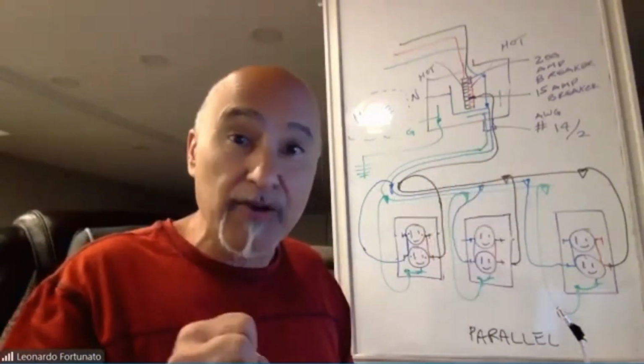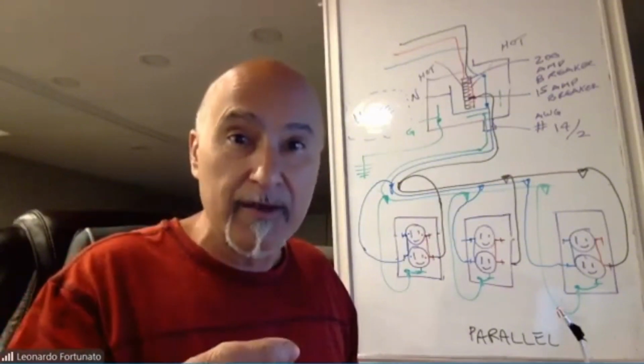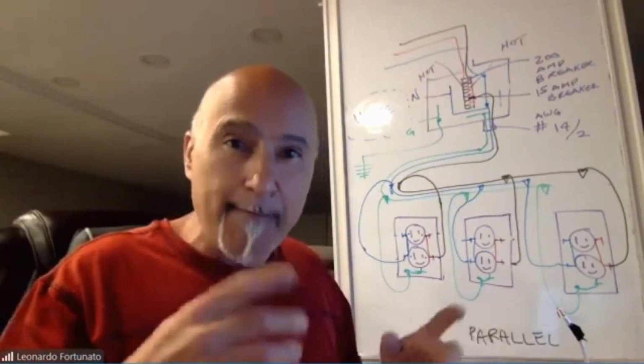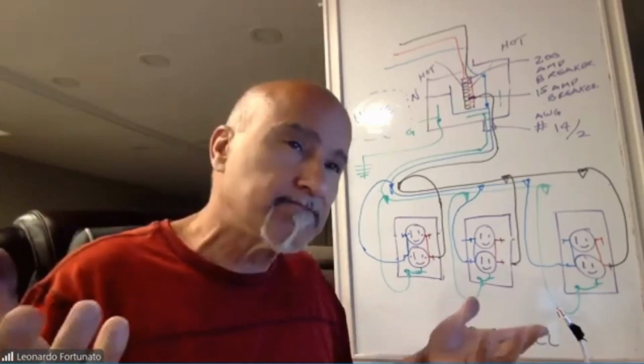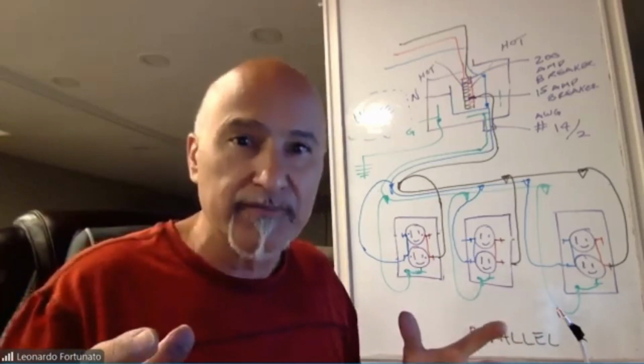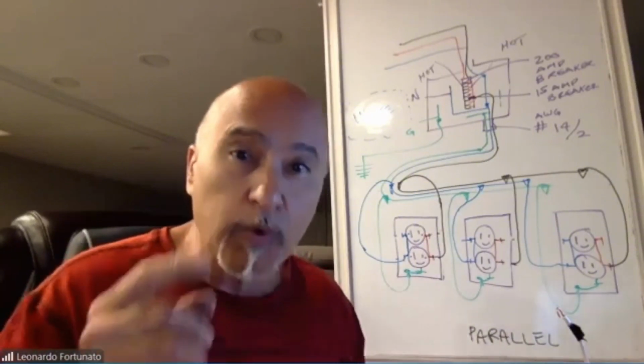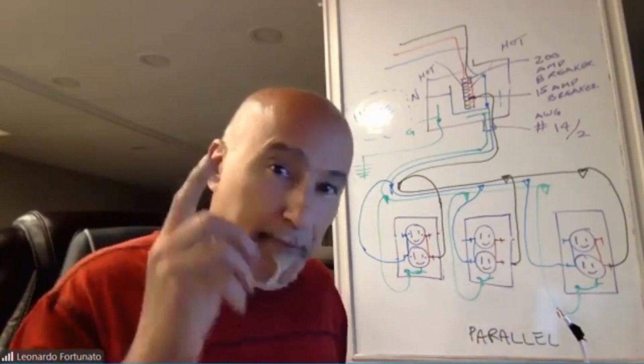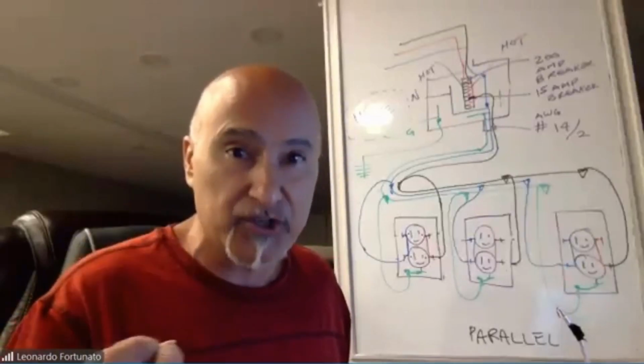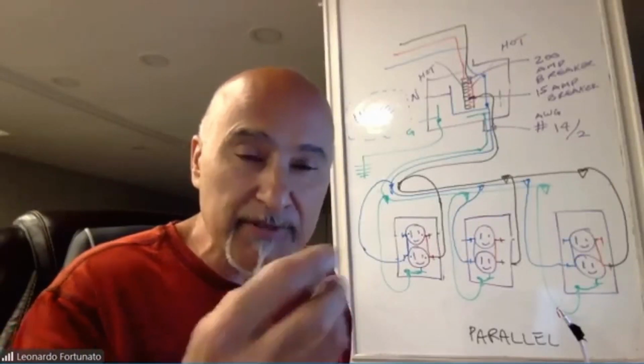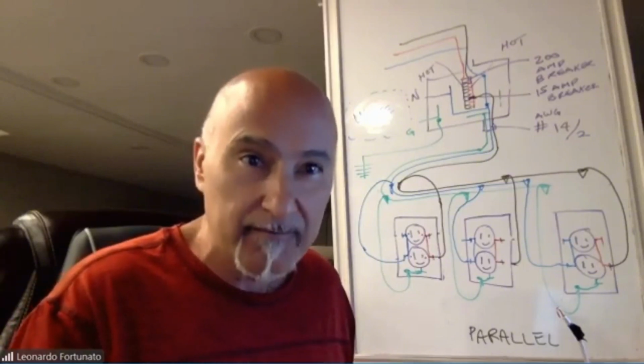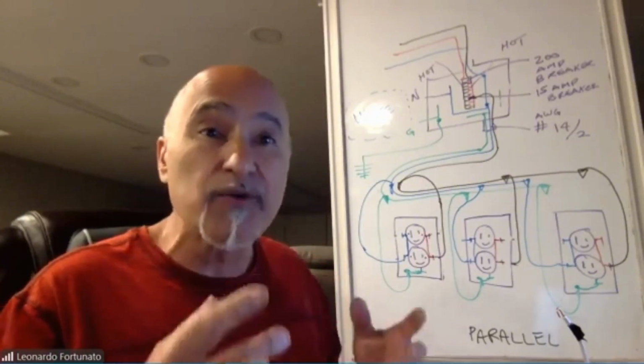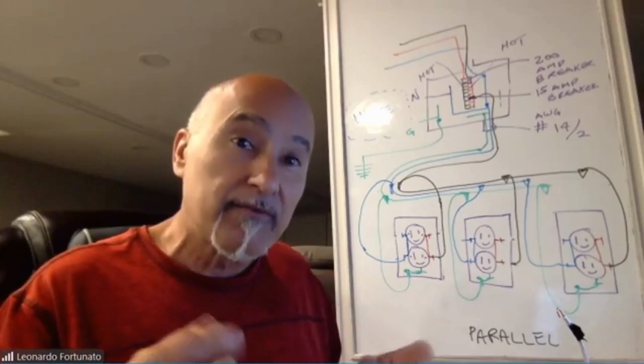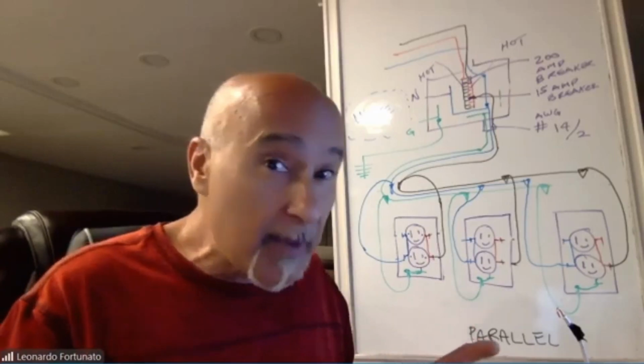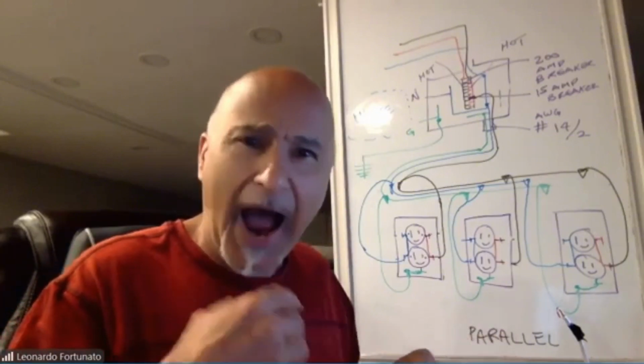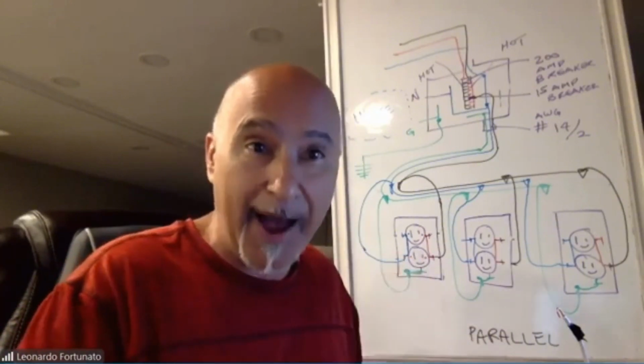But what you just did is draw an extra 40 watts. So imagine we have 10 light fixtures that each require one light bulb. If I put a 60 watt light bulb in each fixture, 10 times 60 is 600 watts. So I'm now using 600 watts of my 15 amp circuit breaker. Safety capacity is 1440, so I didn't even reach half of my safety capacity.